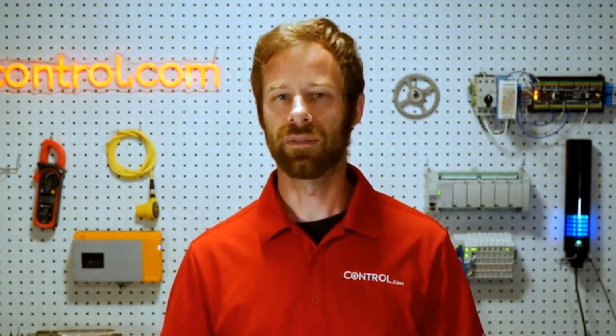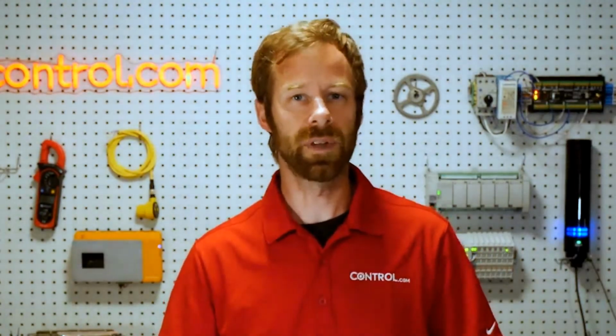But these HART devices are meant to provide bidirectional communication. It's digital signals on top of the 4 to 20 milliamp. The PLC and the device at the ends can filter out the two, with the analog signal still referring to the process data that's being transmitted, but the digital signal is a pulse train that provides digital information, much like a standard digital fieldbus, like Ethernet or Modbus or something like that.